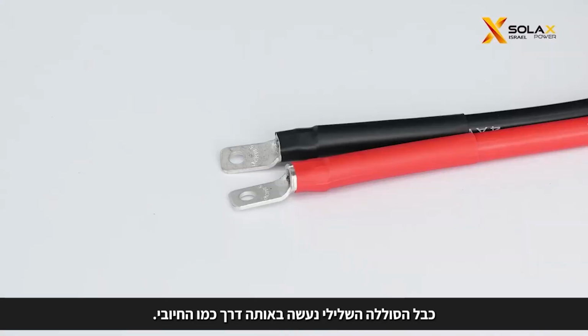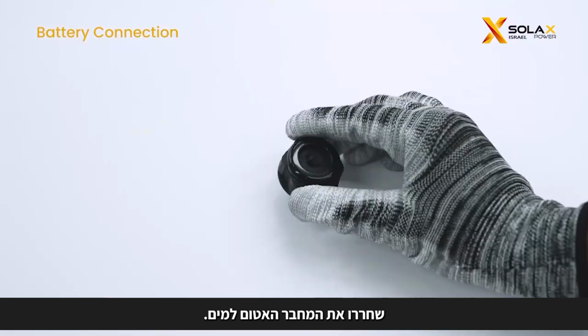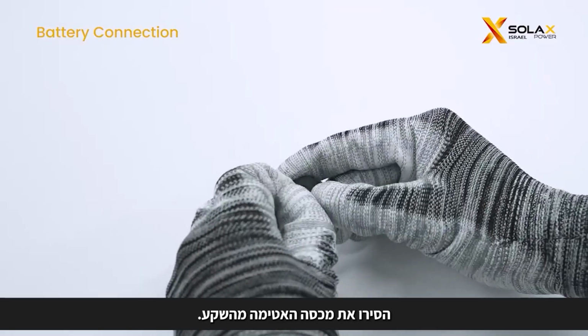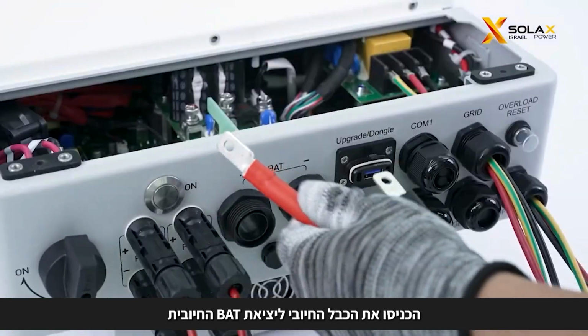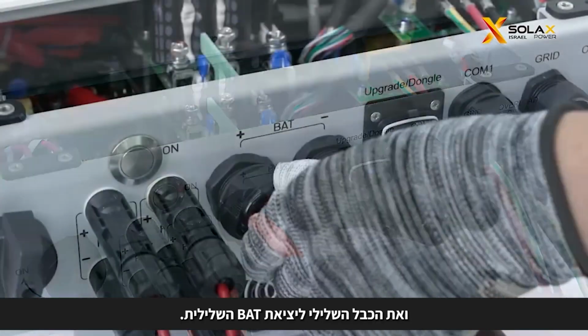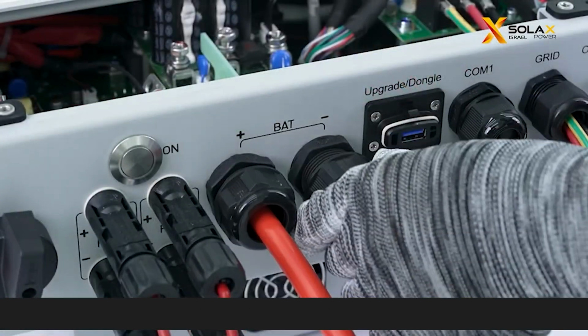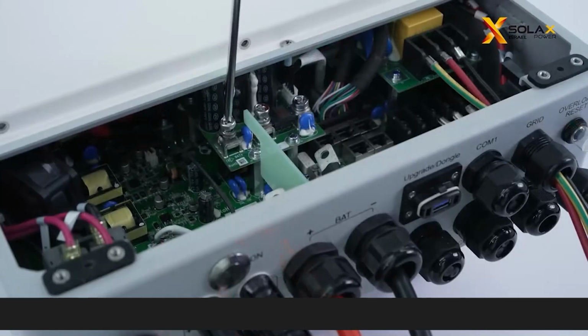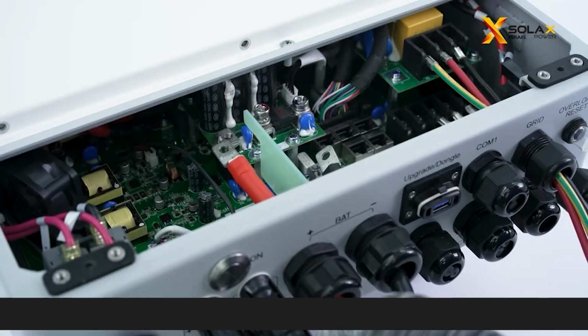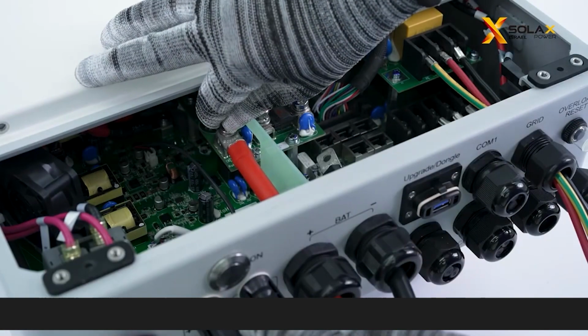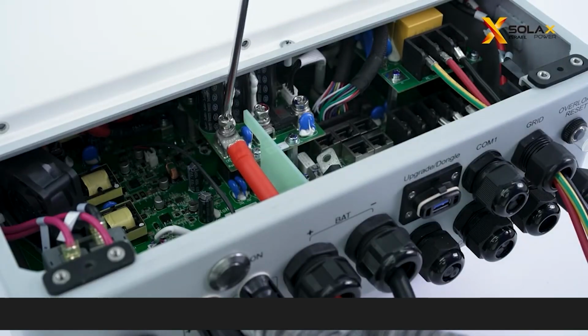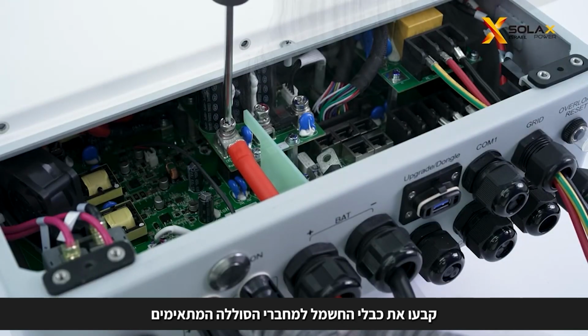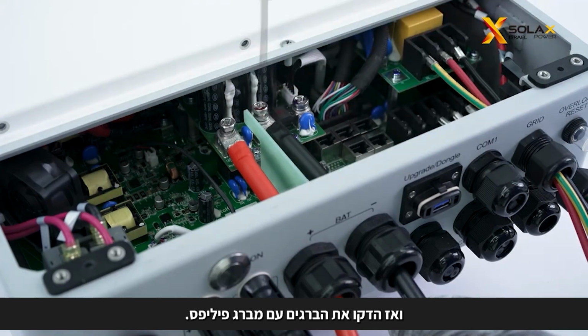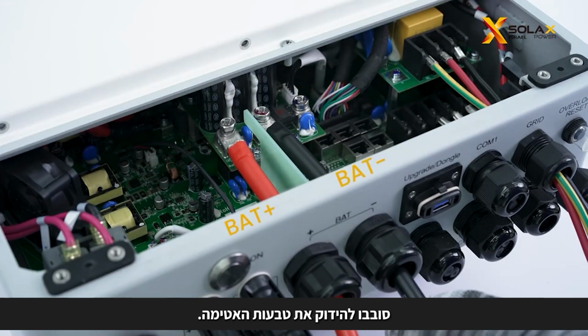The negative battery cable is made in a similar way to the positive battery cable. Loosen the waterproof connector. Remove the sealing cover from the plug. Insert the positive cable into the BAT positive port and the negative cable into the BAT negative port. Remove the screw. Fix the power cables to the corresponding battery connectors, then use a cross screwdriver to tighten the screw. Twist to tighten the seal rings.